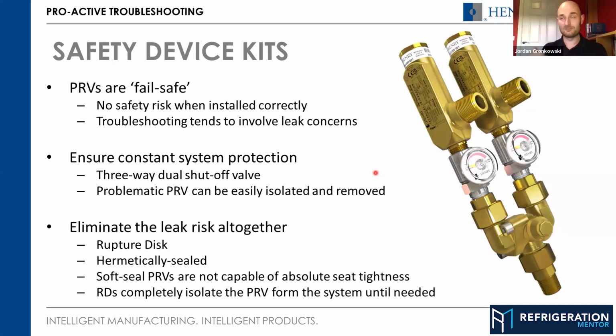So the valve will lift again, but you can't guarantee that it'll be within the plus or minus 3% tolerance on set point of the valve. You can't guarantee that after the massive force and all the debris that's probably been blown across the seat from the little particles inside the system, which all affects the ability of the valve to seal. So you should replace it.